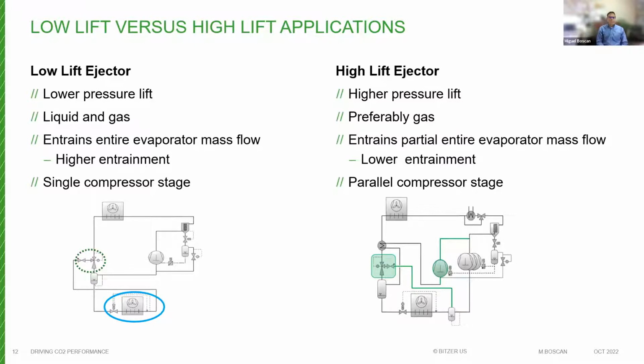There are two different types of applications that ejectors typically will be found in, the low lift versus the high lift. Here are a couple of simple examples of both. In the low lift example, the ejectors act basically as a refrigerant or CO2 pump. They're selected to provide the required force to move the liquid out of the flash tank through the evaporator and back. They're typically used in smaller systems without parallel compression, and so here we see a single compressor stage as the example. The high lift application is more typical of what you would see in the supermarket CO2 rack, and the next slide gets into a little more detail of that in the booster application.